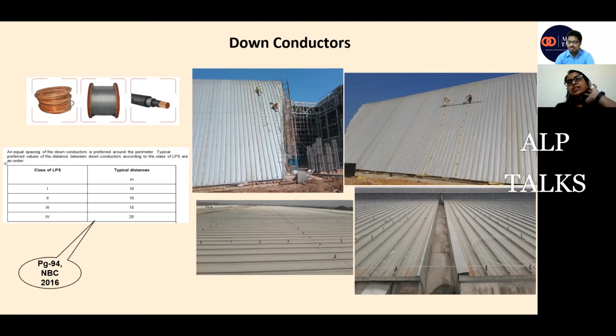Suppose I have a hotel with a glass structure, and I am not able to take the down conductors from the front side. I can take those down conductors as compensating down conductors from the other sides of the structure. But if I am not able to take the down conductors from one side, I should not just skip them. We should take it into consideration and provide compensating down conductors for that side on the other sides of the structure.